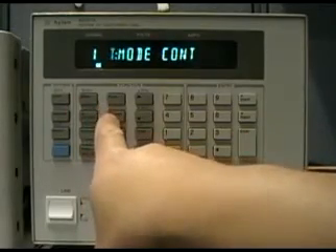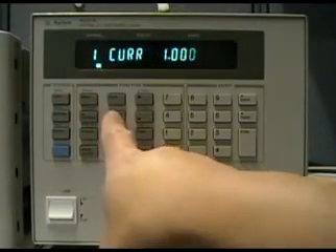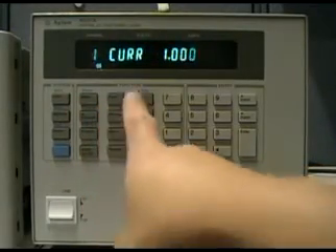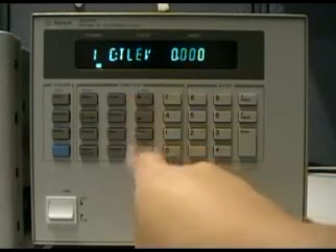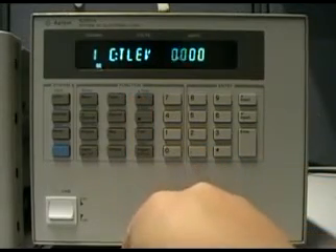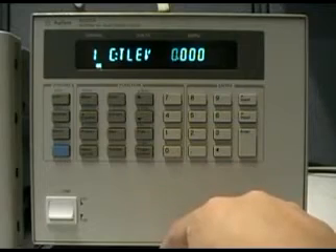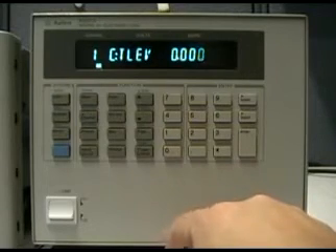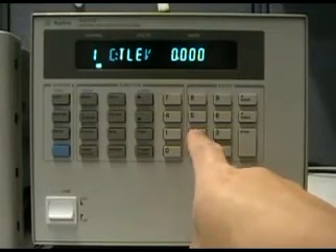Now we'll go to the transient level. We press Current Transient and navigate up to what's called the C Transient Level. We'll set the transient current level at 2A.